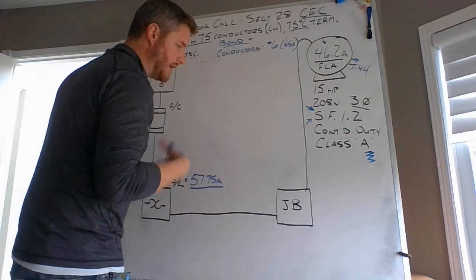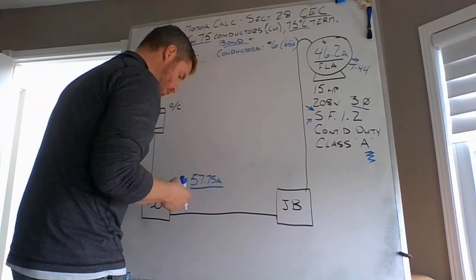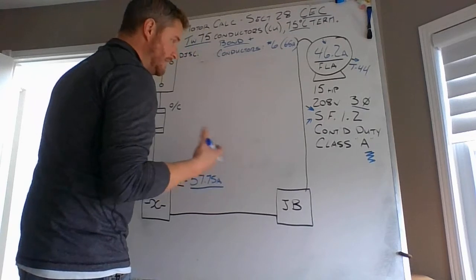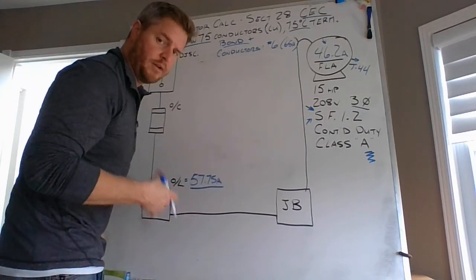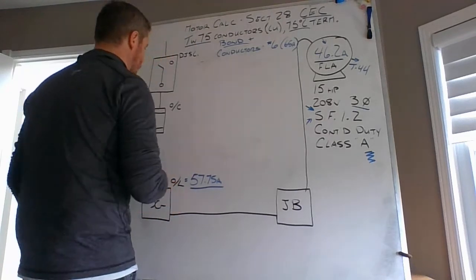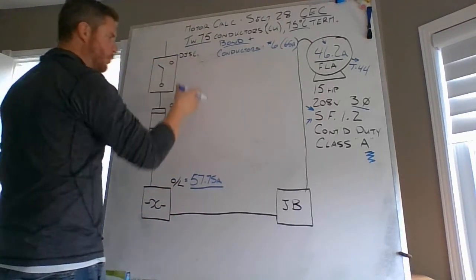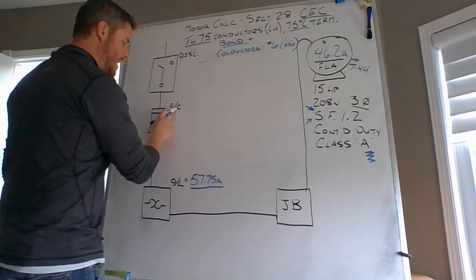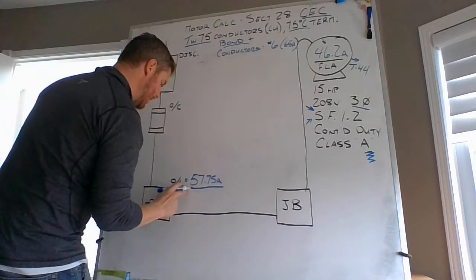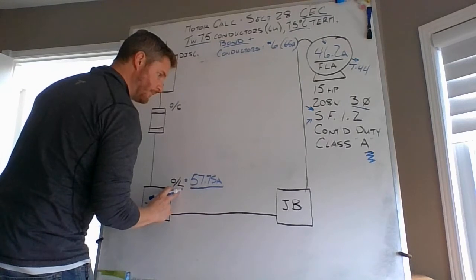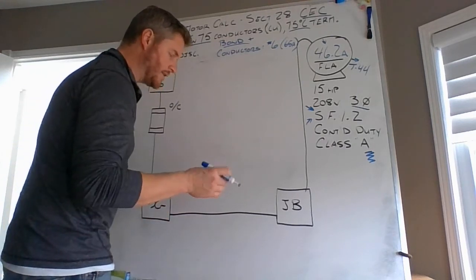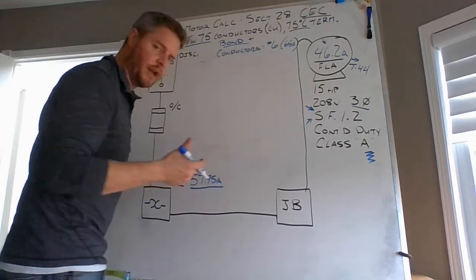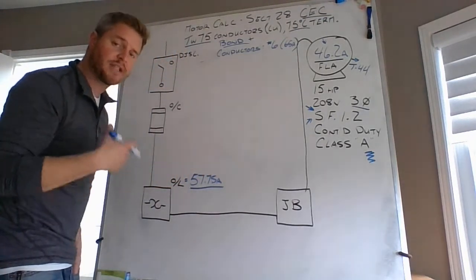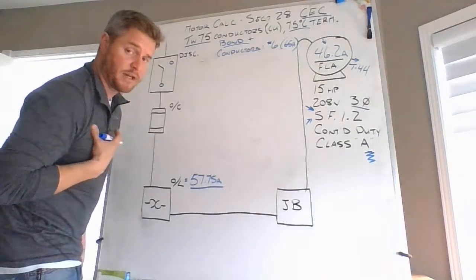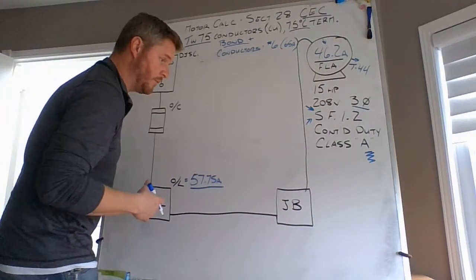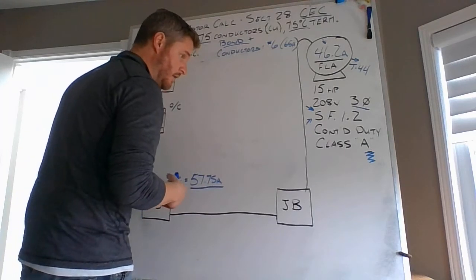And it varies between textbooks. You have to understand that motor control books are based on not the code, different theories of electricity. Okay, so for this example, we have 3 different capabilities of overcurrent protection, but the one thing that's protecting my conductors is my overloads. And those overload contacts are exactly the same ones that you wire in to your motor control circuits every single week in installation methods with either myself or Mr. Pratt. Absolutely. 95 and 96.